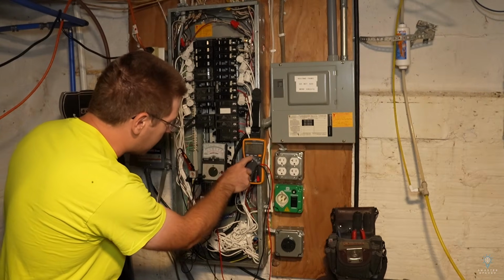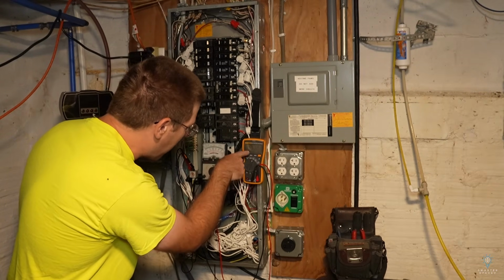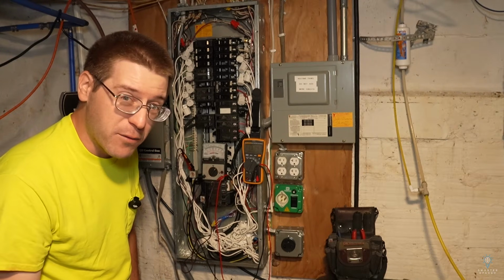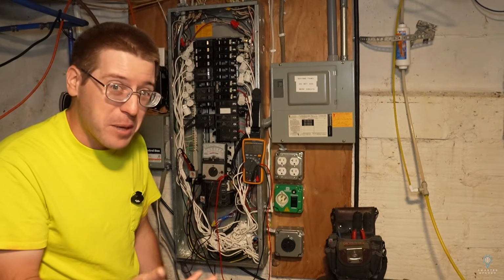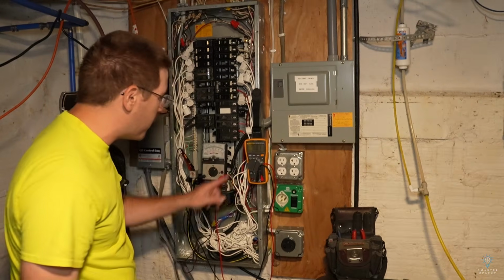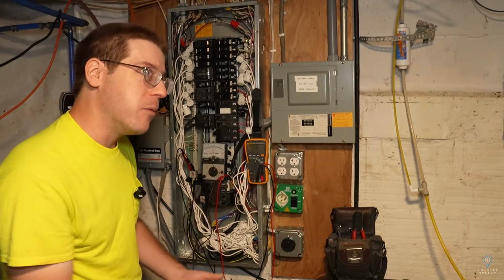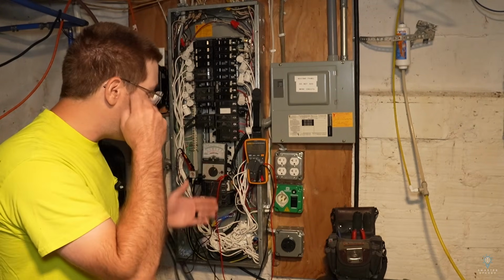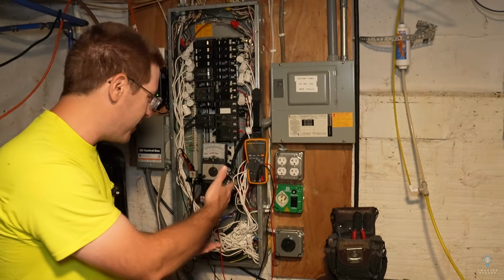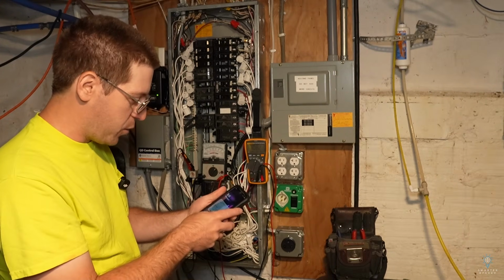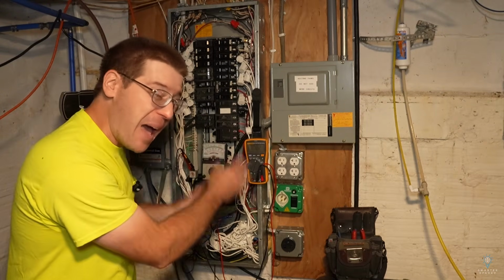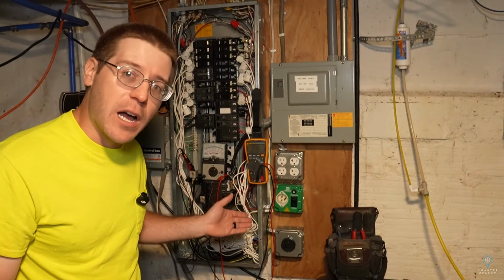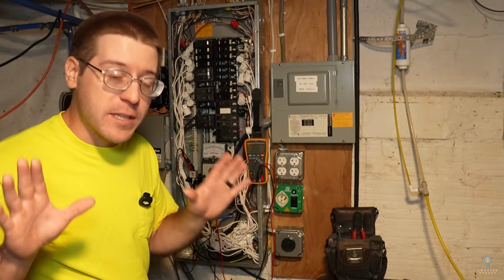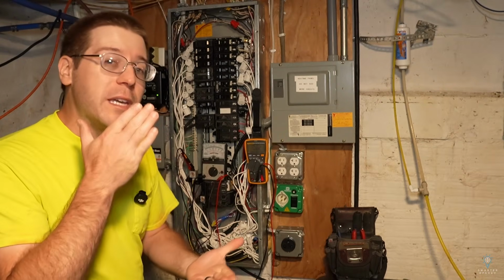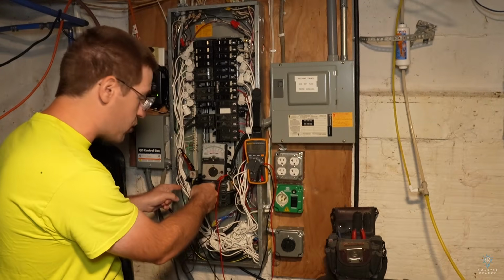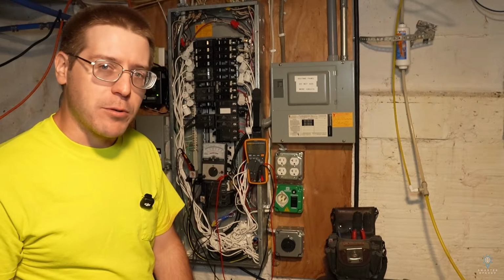Before I shut this down, let's take a look at the min-max values again here. Our max value now on line 2 is 131 volts, and I've been recording this now for maybe 5 minutes. And if we take a look at the minimum value, we've got 108 volts here. So we're looking at, what is that, about 22 volt swing. We just calculated that maximum on the feeder should only be 5% of 120 volts, is 6 volts. So we should see a maximum swing here of 6 volts. We just saw a swing of 22 volts. That there alone is plenty to say we've got a neutral issue here. We can confidently say this is a neutral issue because our voltage line to line stayed pretty solid. We need to start troubleshooting where this neutral is loose.